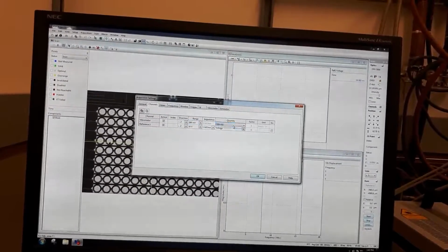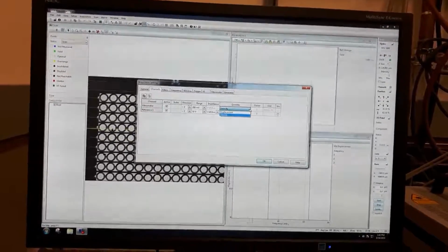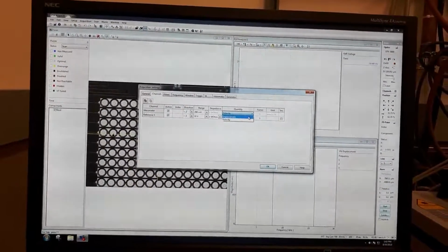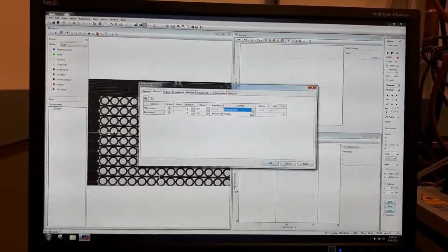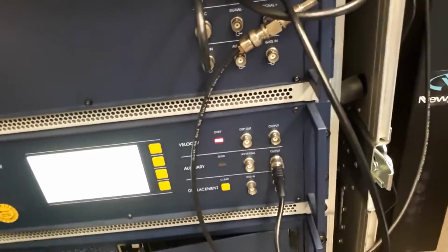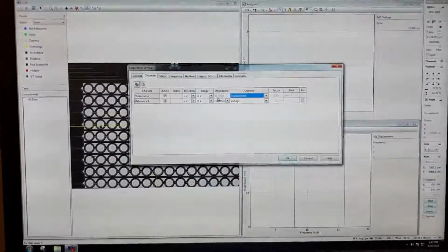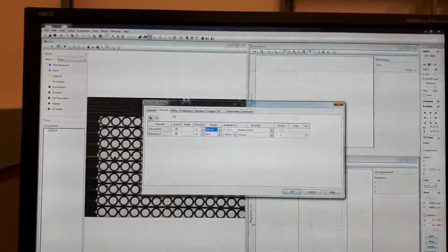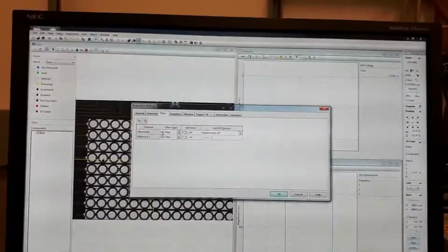And for the type of the measurement, since we are going to work in the megahertz range, click displacement decoder, because that's the same decoder we have connected in the junction box. So now displacement decoder and low voltage range, that's your starting point. Next tab, filters.